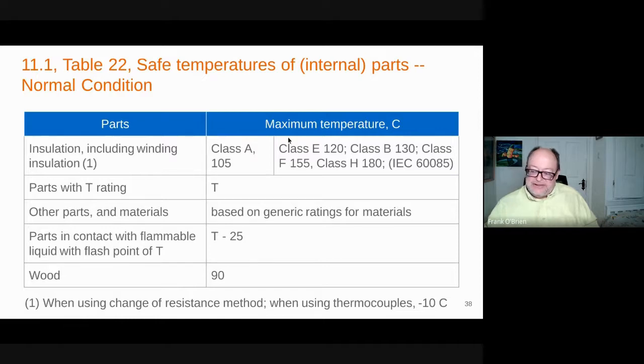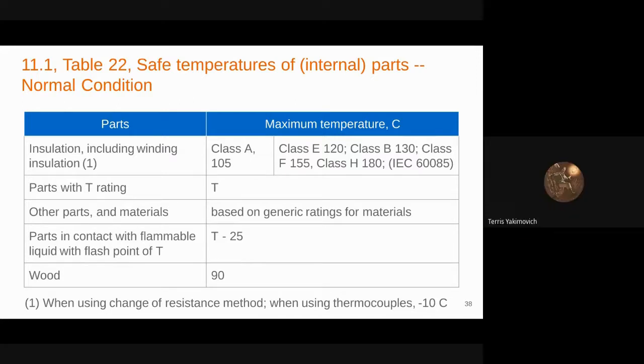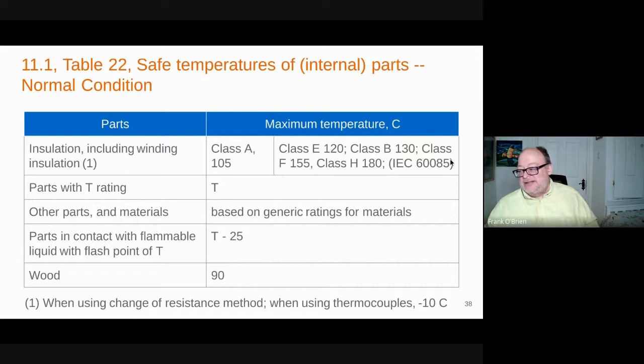By default, all insulations considered class A, and there's a limit of 105, but that's in a 40 ambient, or whatever your ambient is, if it's higher, the max. And so that rise is 65, I think. Yeah. And if you had insulation classes that are higher, those vendors evaluate the materials together for that. There's an IEC 85 as well as a UL standard. So by default, you want to comply with at least the 85. And so sometimes you can be class B, F, or H. H is very high stuff, like Nomex and Teflons.